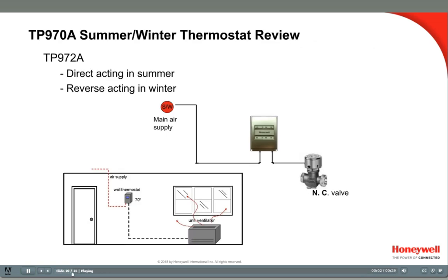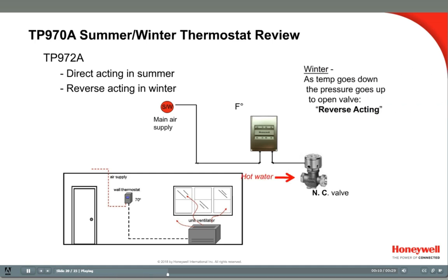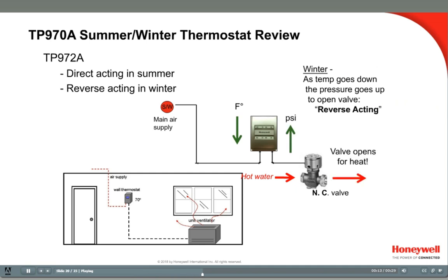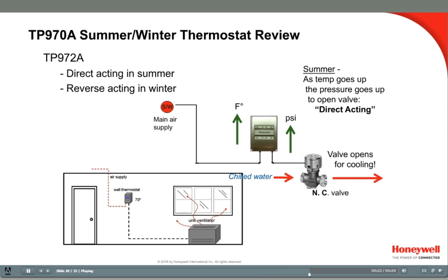Next, I will show you some applications using Honeywell pneumatic relays. Some of the examples use the TP972 summer-winter thermostat. Summer-winter thermostats are needed when the same valve and coil is used for cooling in the summer and heating in the winter. In the winter, the thermostat is reverse-acting for heat, but in the summer it switches to direct-acting for cooling.